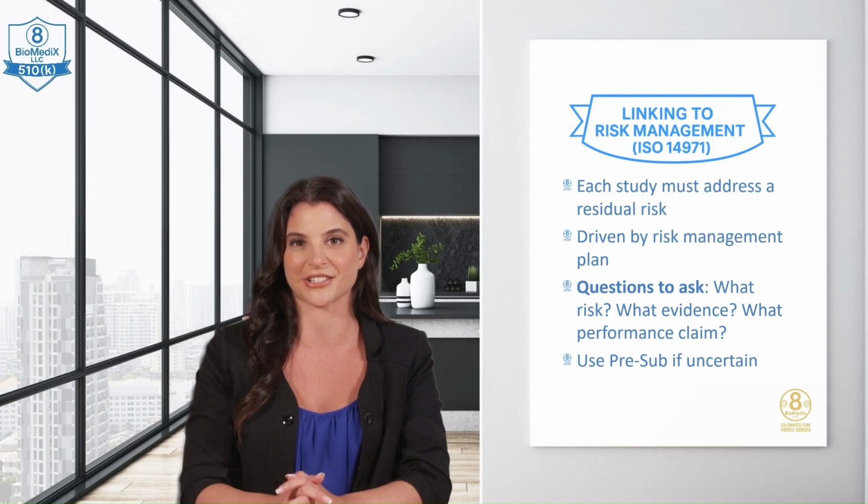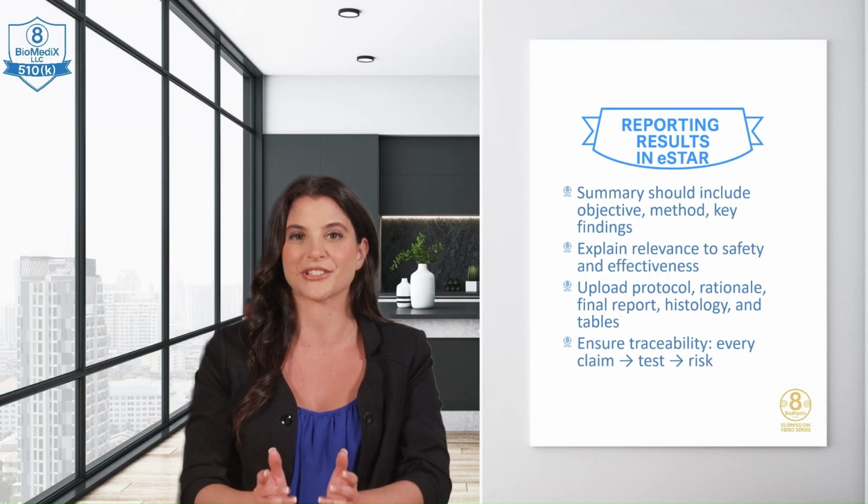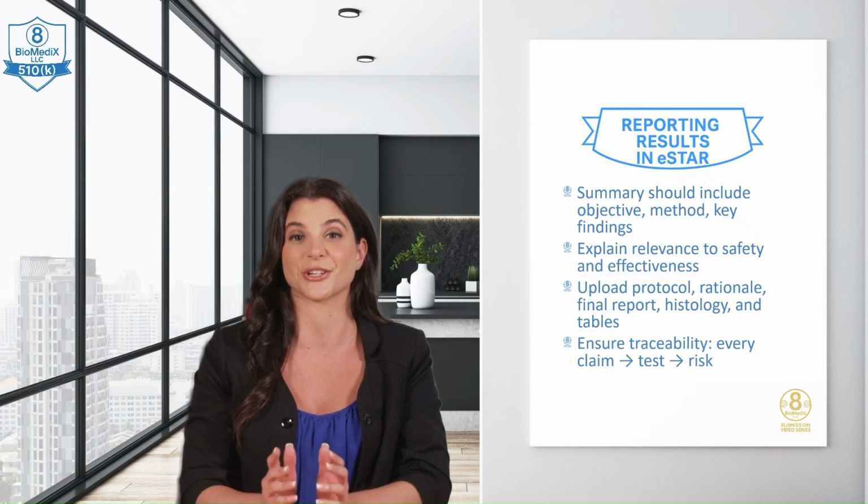Reporting results in eSTAR. So, how do you report clinical or animal study results in eSTAR? Start by providing a concise summary, objective, method, and key findings. Then, explain how these results support your device's safety and effectiveness. Think of it as, here's what we tested, here's what we found, here's why it matters.